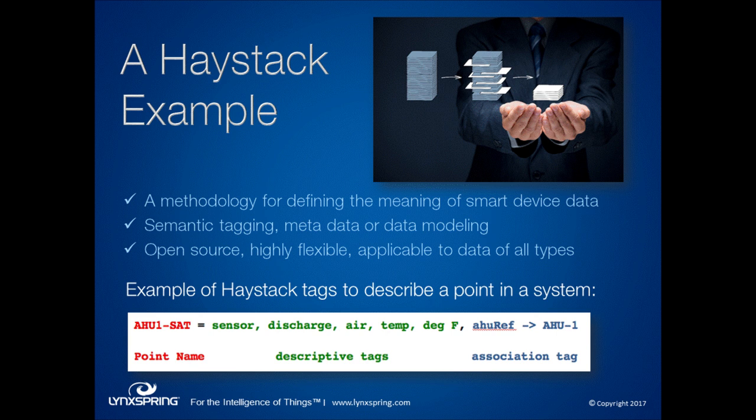Looking at an example: in red we have a name — maybe AHU1-SAT, the name the BAS has. But the tags in green describe what it is. These are descriptive tags: it says it's a sensor value, it's discharge air temp, and its units are degrees F. Then in blue we have another type of tag — a tag that talks about ownership or relationship. It says this is tied to a piece of equipment known as AHU-1. That's a real example of Haystack tags at work. Notice that they're readable.